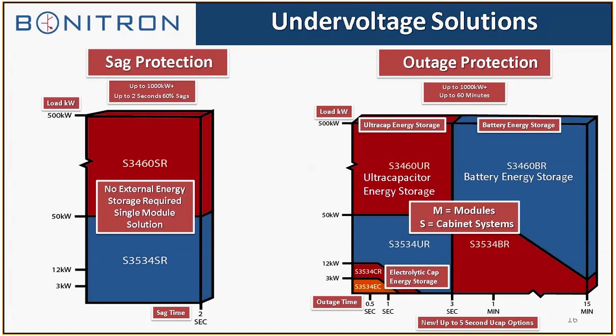So on the left is the sag protection. Kilowatts to time, up to 2 seconds. The sag ride-throughs will do up to 2 seconds. And then the outage protection, or the outage ride-throughs, once again, kilowatts per time. If you look at the outage protection block there, on the very bottom left, we can provide electrolytic capacitor energy storage, which is more economical than ultracaps. For 12 kilowatts and below, up to 1 second, we can do electrolytic caps. Anything greater than that, we would go to ultracaps.